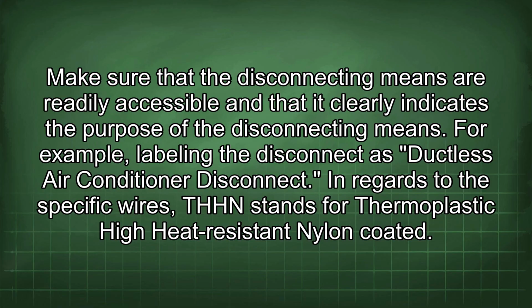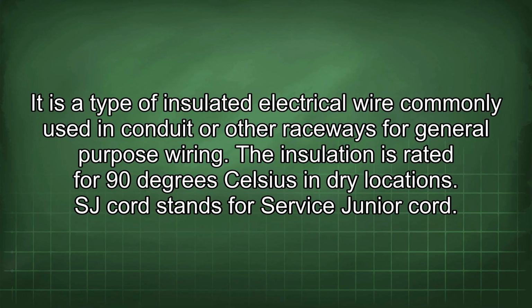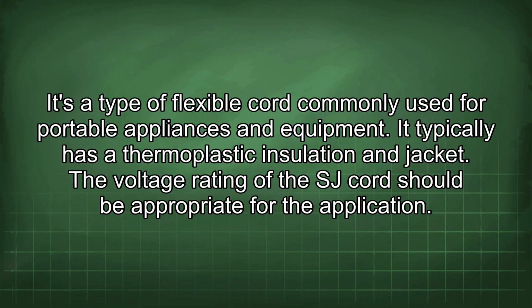In regards to the specific wires, THHN stands for thermoplastic high heat resistant nylon coated. It is a type of insulated electrical wire commonly used in conduit or other raceways for general purpose wiring. The insulation is rated for 90 degrees Celsius in dry locations. SJ cord stands for Service Junior cord. It's a type of flexible cord commonly used for portable appliances and equipment. It typically has a thermoplastic insulation and jacket. The voltage rating of the SJ cord should be appropriate for the application.